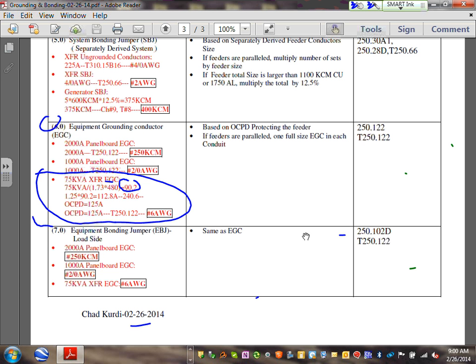So on the primary side, you need the primary conductor current. So take the 75 kVA divided by the voltage, that gets you 90.2, multiply by 1.25. That'll get you 112.8. If you go to 240.6, that will get you an overcurrent protection device maximum of 125. You take that 125, guys, to table 250.122, and that will get you number 6. So your equipment grounding conductor, Karen, and your equipment bonding jumper at the load side, can you see that, is not smaller than number 6. Any comments, guys, about the equipment grounding conductor coming to the transformer?